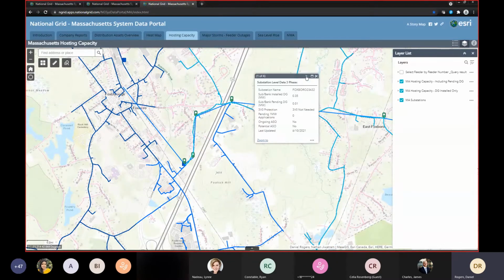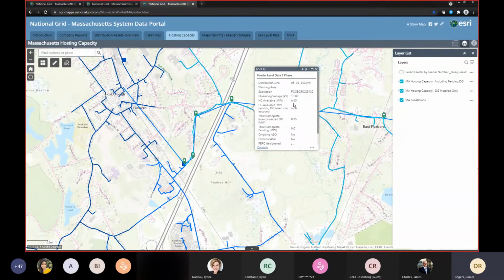And then jumping into some data discrepancies that we have had, just because when I'm using this map and when others are going to be using the map, when we're calculating hosting capacity, we want it to reflect real numbers. So when I calculate the hosting capacity and take into account connected DG, these numbers reflect the DG that I have taken into account that directly affects the hosting capacity. So say that there was a battery connected and it is in the NCAP documentation and it aggregates up to that line, you will see that there is another 1.5 megawatts of connected, but that DG, specifically the battery, shouldn't be limiting the hosting capacity if it was originally there to increase the hosting capacity.